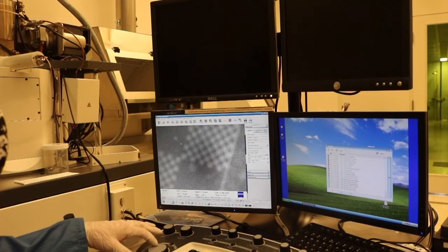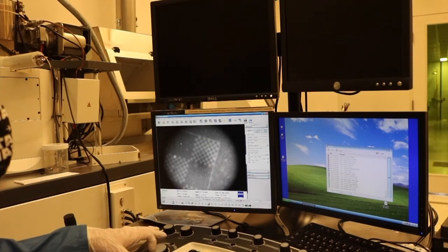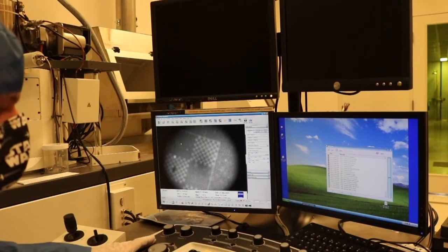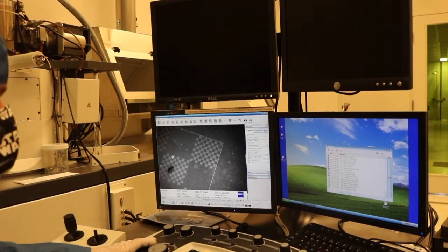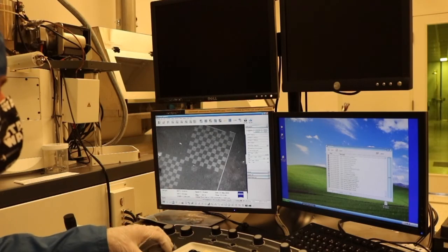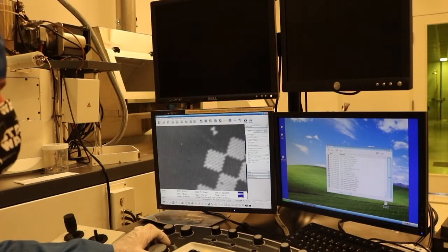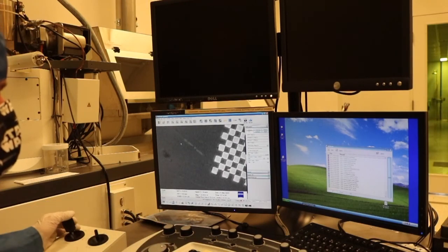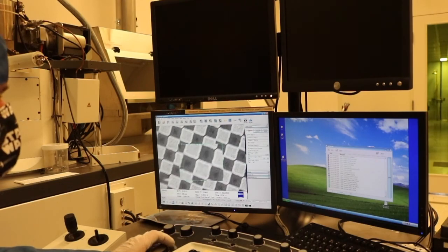It's always good practice to come to the magnification control, go completely counterclockwise, anti-clockwise, and bring the magnification to its lowest possible setting, and then come to the focus control and focus the image roughly. Once the image is roughly focused and things look like they might be in focus, we can increase magnification until the image is out of focus, and then we can make adjustments again. And we just repeat this process until we get to a point where we can't make the image any better.